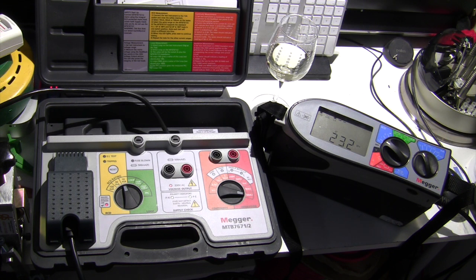If we saw a result come back of, say, 50 milliseconds on this test, then ordinarily that would appear to be a pass because it's within 300 milliseconds that the British Standard recommends. But under the simulated conditions, it should react within 40 milliseconds, and if it doesn't, it's a fail. So we're going to squirt that in, and we should see a number below 40 milliseconds at rated current. And we're getting 36.4. Super duper.